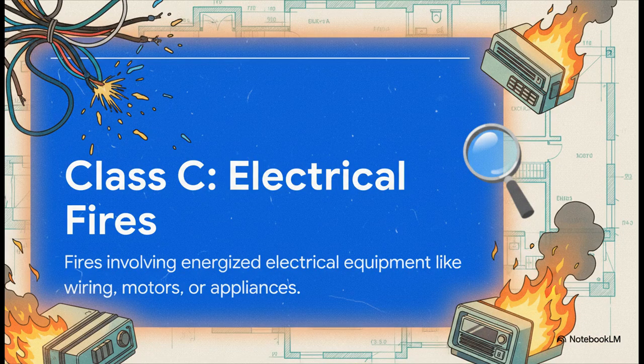Okay, Class C is a bit of a curveball. What's super interesting here is that it's not really about what is burning, it's about the situation. We're talking about a fire that involves energized electrical equipment. The huge danger here is the shock hazard. So, think C for current. In fact, if you manage to cut the power, it often just becomes a plain old Class A fire.